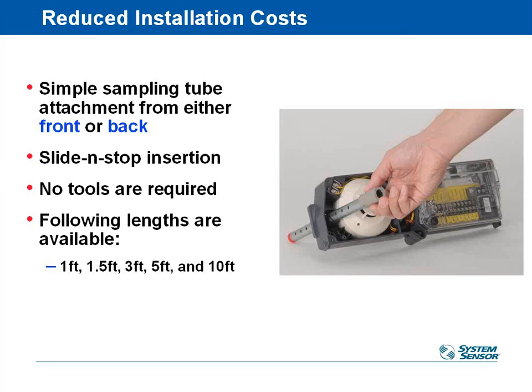The sampling tubes are also pretty convenient. They can be installed from the front or the back side of this guy. So this particular picture here shows us installing it through the detector. So the detector could already be mounted on the duct, and then I can go ahead and slide my sampling tube in. In this case, I'm showing a 1-foot sampling tube. Slide him right in, and he'll click into place. They're available in 1, 1.5, 3, 5, and 10-foot sections. 5 feet being the most common by far.